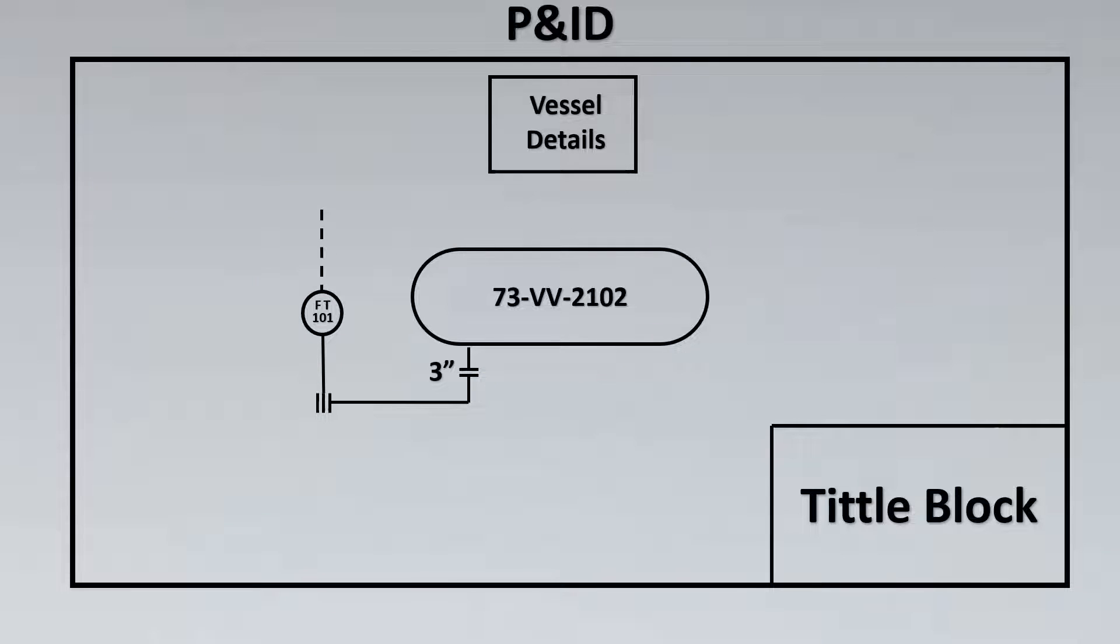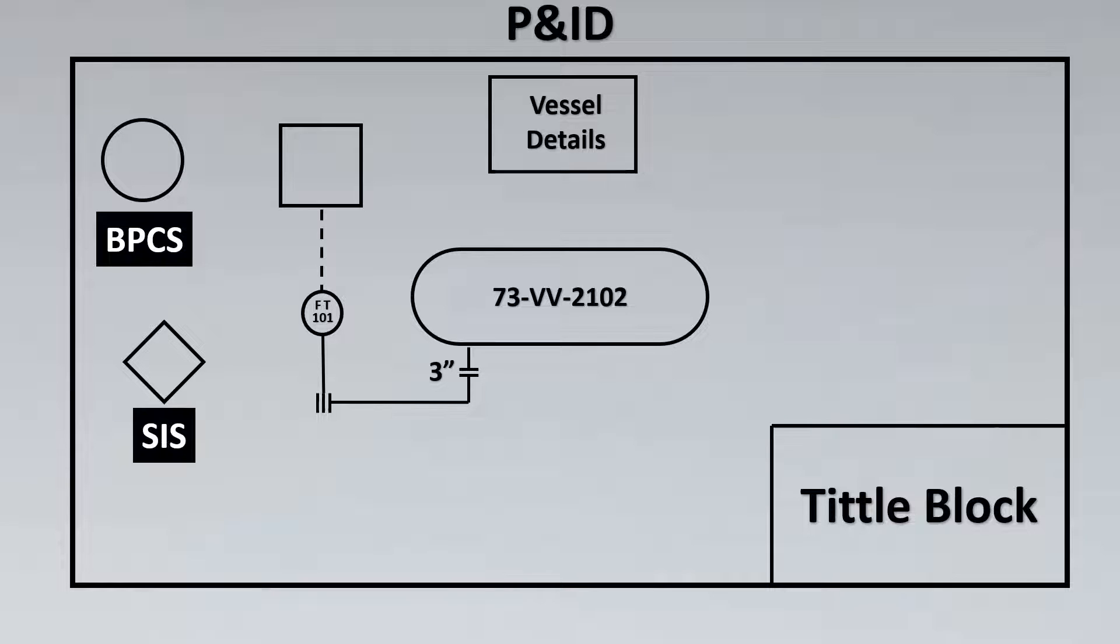Now you see here there's another signal coming from FT which is going to a square box. Remember square box is a very important thing, and the square box has something inside of it which is either a circle or a diamond shape. Now the circle stands for BPCS. Don't be confused, it's a very simple word which means basic process control system. But usually in the instrumentation world we call it DCS, and this is SIS. So remember DCS and SIS are the two systems especially which are put in the control systems, and here either of this will come inside the square.